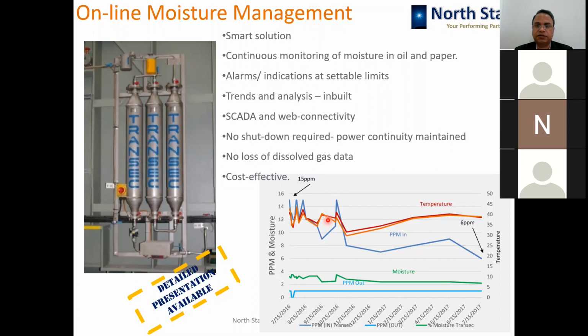This is an online filtration system which you can put on the transformer, and it will keep on drying the oil as well as insulation. Over a long period, you will find that your transformer is running totally dry. So conventional filtration cycles will not be required after you put this system. Maybe after 1 or 2 years, the filtration is not required.